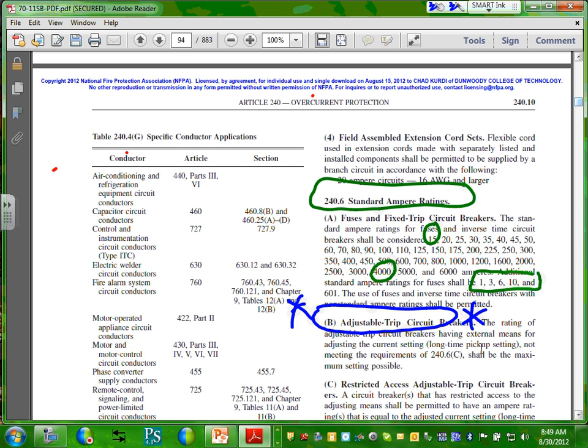Okay. Now, based on the criteria that I have, what was the calculation, Jeff? 42 and a half. Okay, 42 and a half. No, go up. Here's a 40, 42 and a half. What was the standard then? 45. It allows you to go up. Do you have to go up? No. Can I go down? Yes. I can go down, but you can't go higher than one step up. Everybody knows why I went to 45? Aaron? Okay. Awesome. So we got that one here.